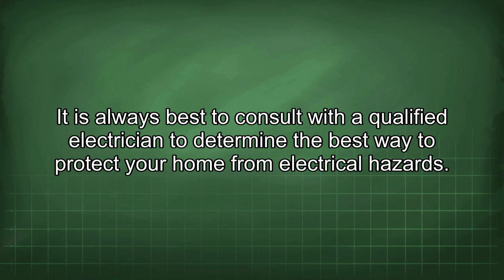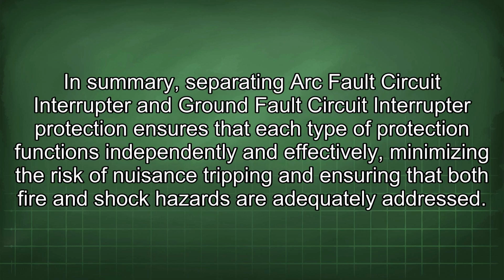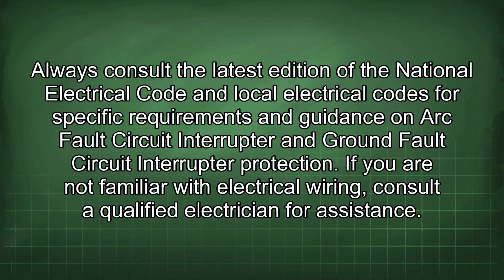In summary, separating arc fault circuit interrupter and ground fault circuit interrupter protection ensures that each type of protection functions independently and effectively, minimizing the risk of nuisance tripping and ensuring that both fire and shock hazards are adequately addressed. Always consult the latest edition of the National Electrical Code and local electrical codes for specific requirements and guidance on arc fault circuit interrupter and ground fault circuit interrupter protection. If you are not familiar with electrical wiring, consult a qualified electrician for assistance.